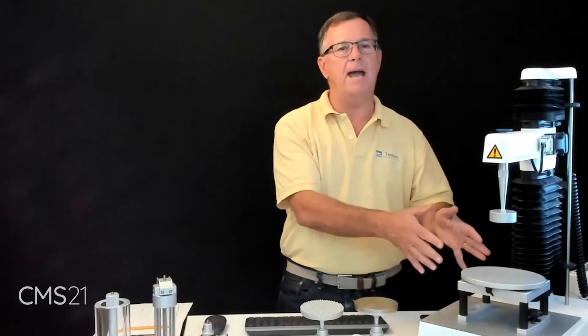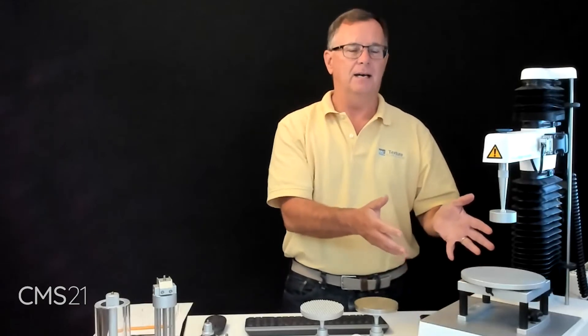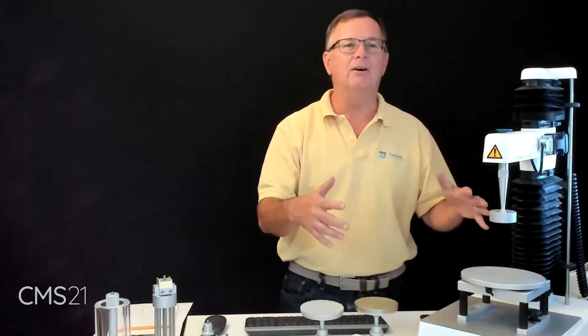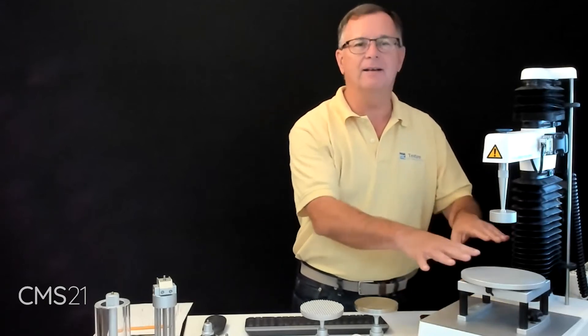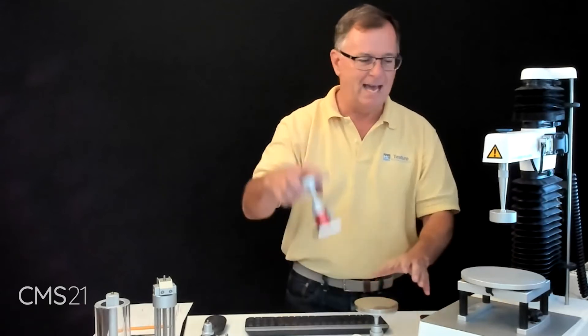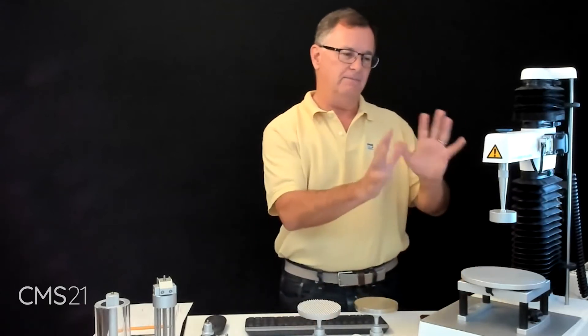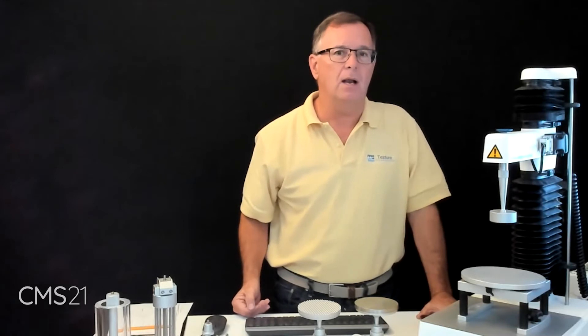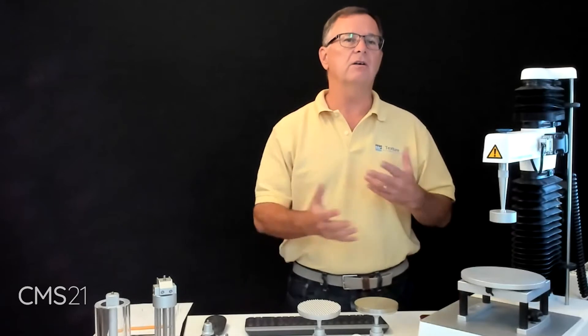A couple questions that come to mind - really starting off with what's the learning curve for getting familiar with one of these systems? Well, it takes about 45 minutes to unpack and install the software when someone first opens it out of the box. Just put the instrument on the desk, plug all the cables in, attach by screwing down a probe or two. So setting up the instrument is pretty easy.